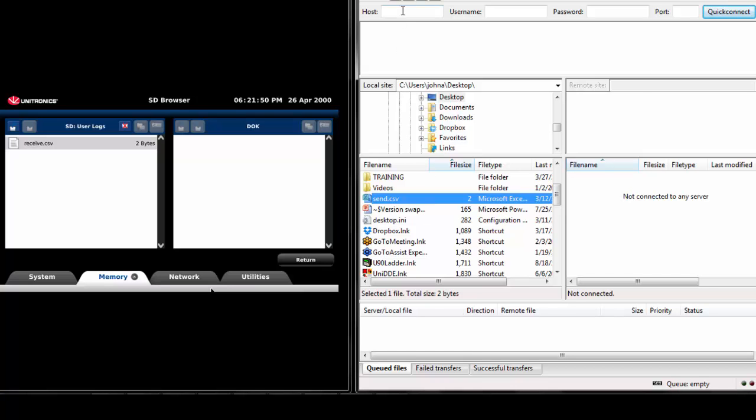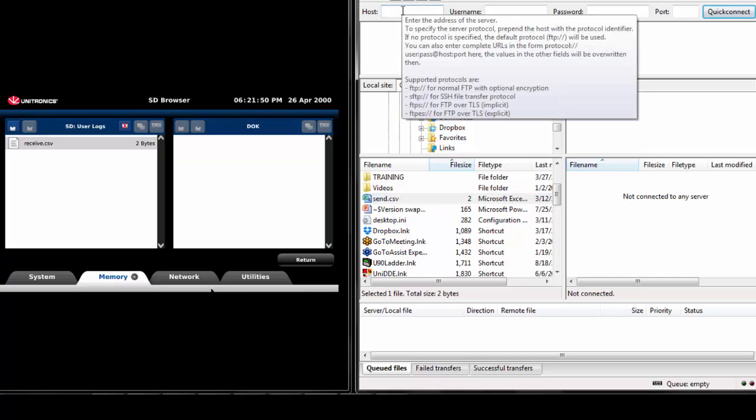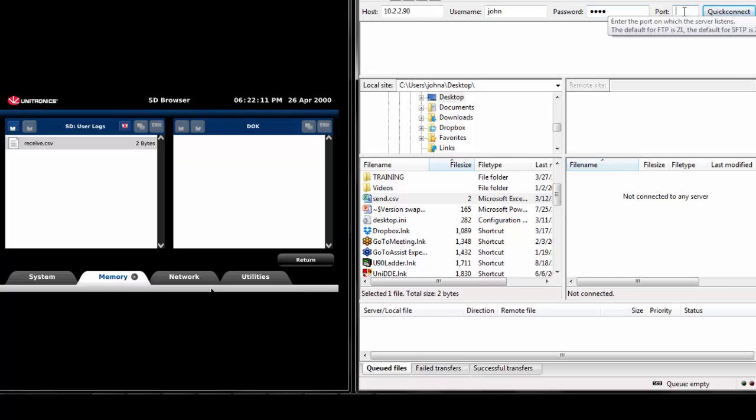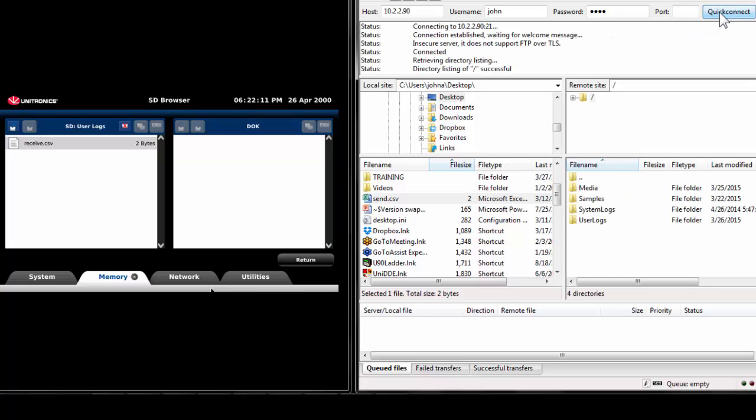First, enter the UniStream IP address in the host bar. Next, enter the username and password that were created within UniLogic. Lastly, enter port 21, as this is the default FTP port. Select Quick Connect and connect to the server.